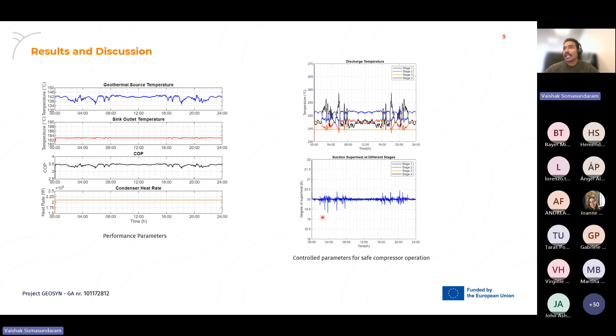During the operation, the COP of the heat pump is also being evaluated, and it is roughly observed to be around 3.5. Here in the same slide on the right side, how the control parameters are varied is also shown. In the first graph where the discharge temperature is shown, we can observe that the discharge temperature is kept well below 270 degrees centigrade. So please note that this is based on the initial, preliminary dynamic model. When we accurately estimate the pressure drops and also the efficiency of the compressors, this graph can have some changes in the behavior. Similarly, the degree of superheat on each stage is also shown here, and it is maintained well between 19.5 to 20.5.